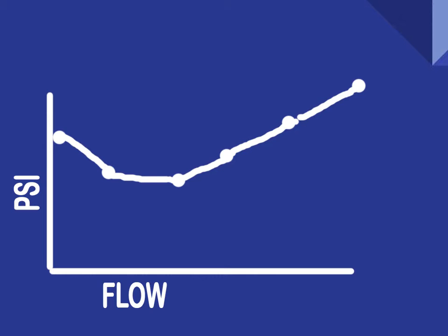The last thing is something we briefly touched on, valves. But valves aren't just a standard adjusted equivalent length. We're talking about devices that have their own loss or gain curves. By saying they have a curve, we are saying that they have a different pressure loss impact depending upon the flow, so it can vary from calculation to calculation. With a variable such as that, it often makes sense to have a node so that it's easy to compare the calculated loss to the official device information's loss chart.